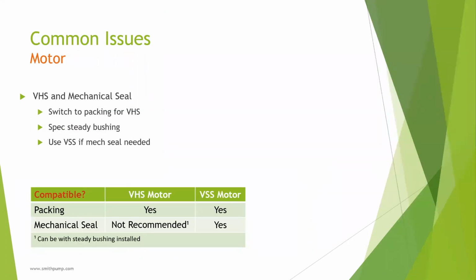So speaking of seals, let's talk about motor and seal compatibility. Motor and seal choices have a direct relationship with each other, and they're not 100% interchangeable. Take a look at the green chart here. Packing is acceptable to use on both a vertical hollow shaft and vertical solid shaft motor. Why is it we can't use just any motor on any seal? It comes down to shaft runout.